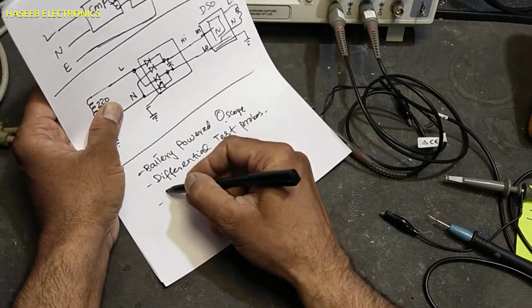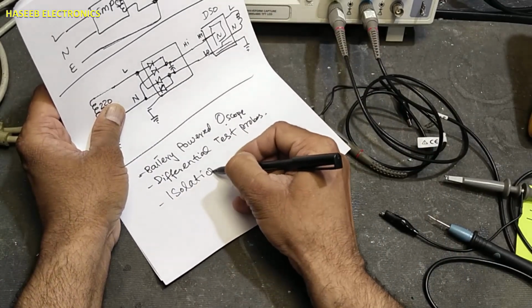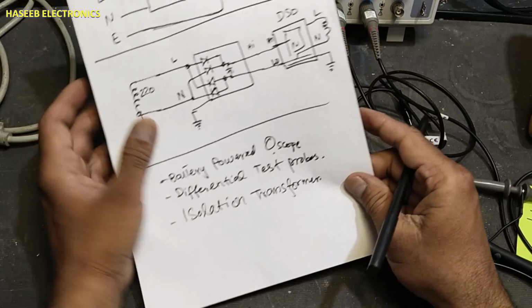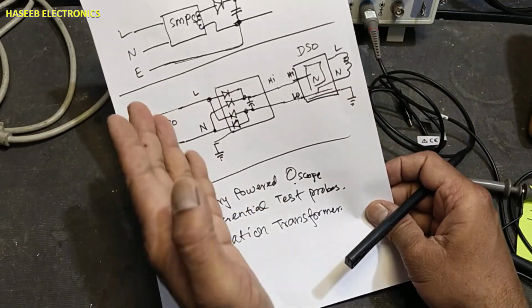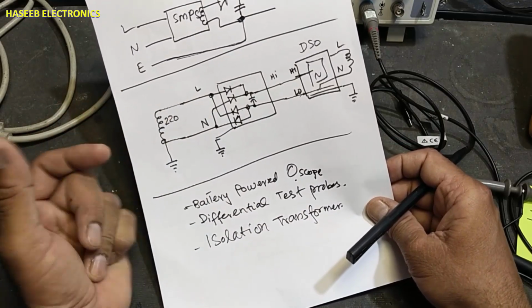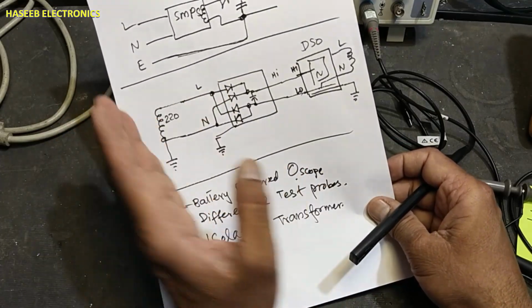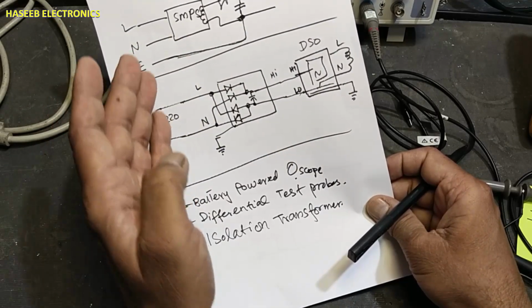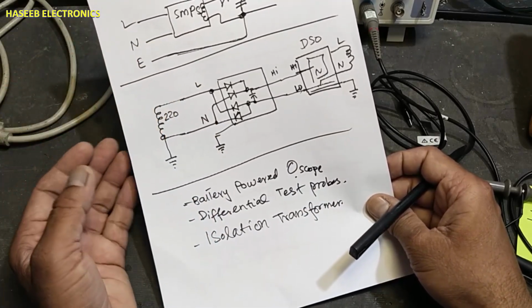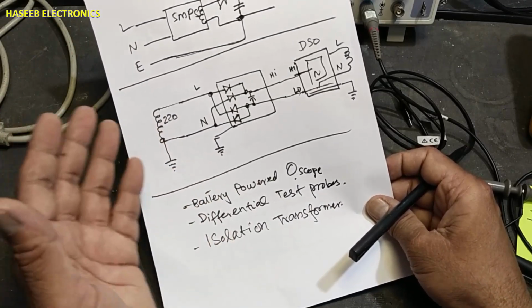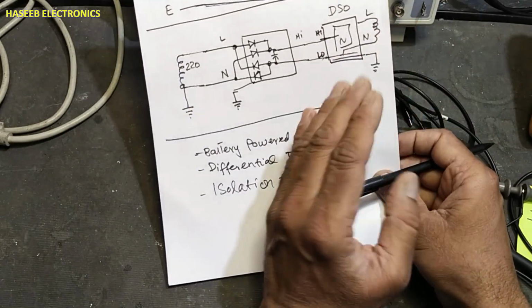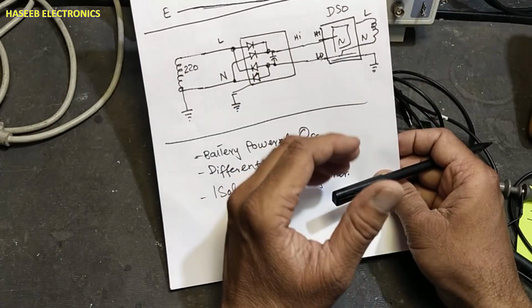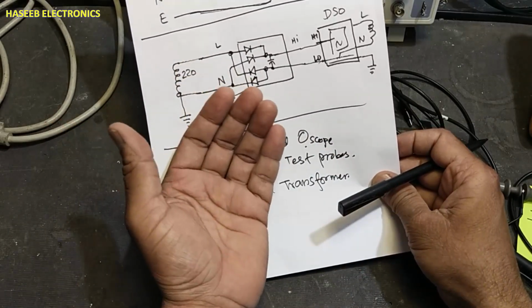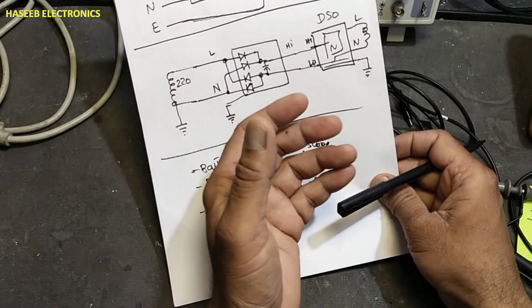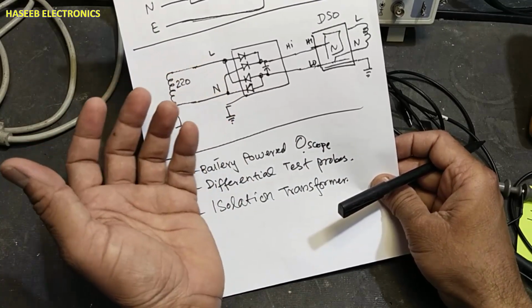Then we can use an isolation transformer. We can isolate this circuit. We need a very heavy size isolation transformer, because if you want to power up your test bench using an isolation transformer, maybe you will need 5000 watt, 5 kVA, 6 kVA, 10 kVA, because when you are testing any job, you need isolation and you need heavy current based on the type of fault, maybe an input short circuit. A small transformer will not be able to detect the fault.